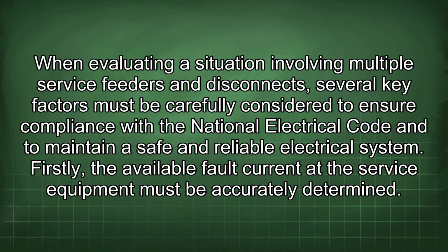When evaluating a situation involving multiple service feeders and disconnects, several key factors must be carefully considered to ensure compliance with the National Electrical Code and to maintain a safe and reliable electrical system. Firstly, the available fault current at the service equipment must be accurately determined.